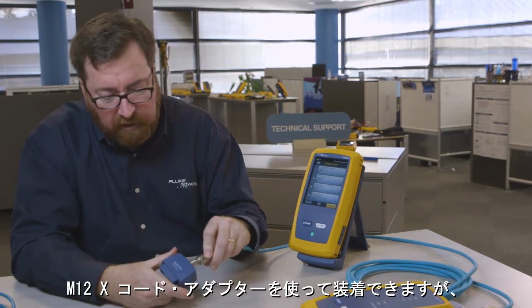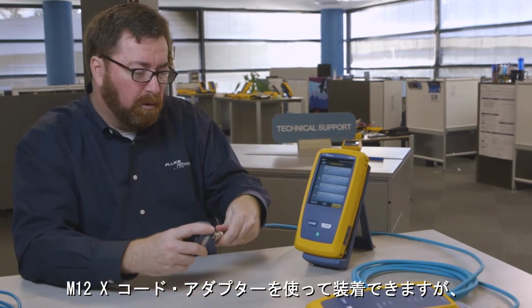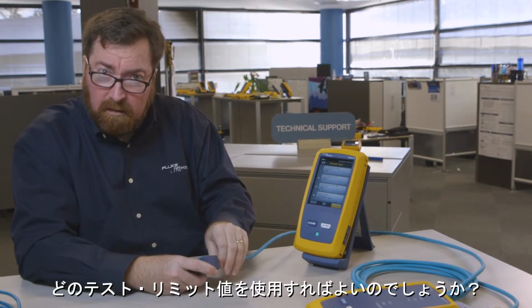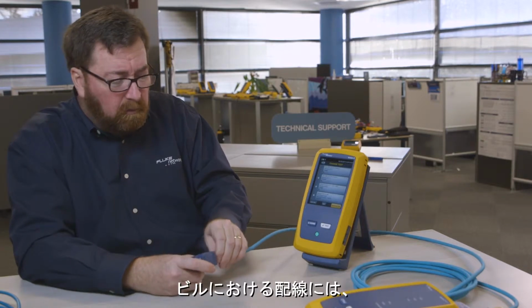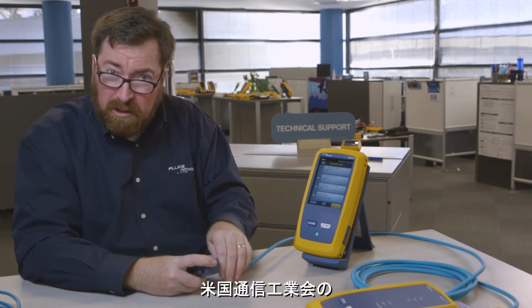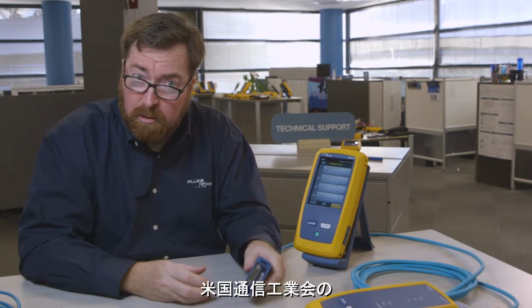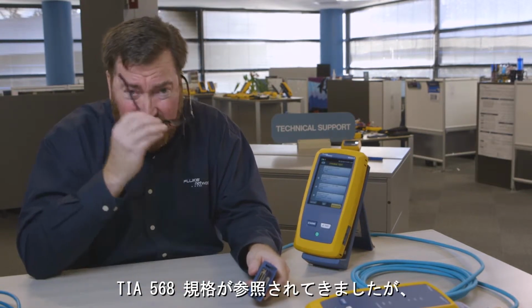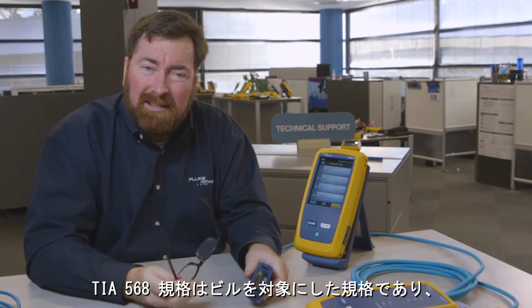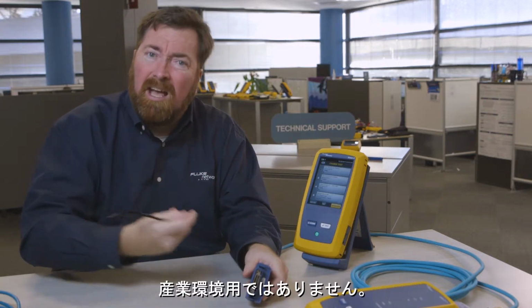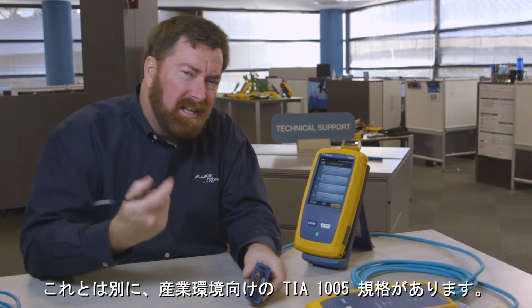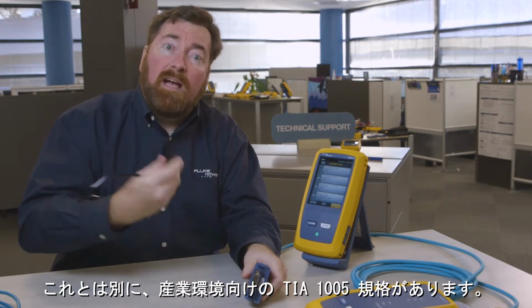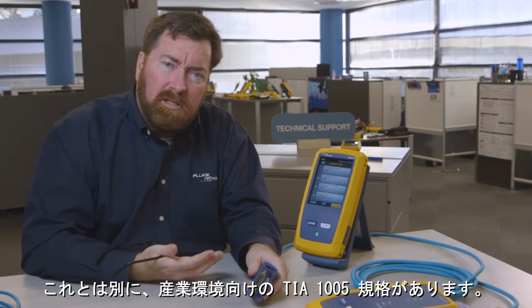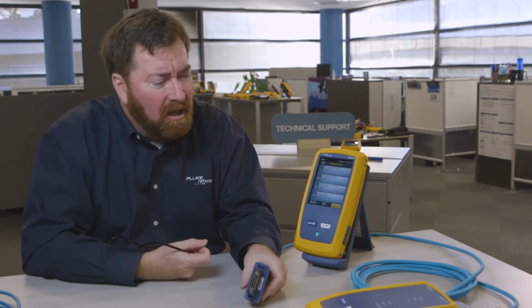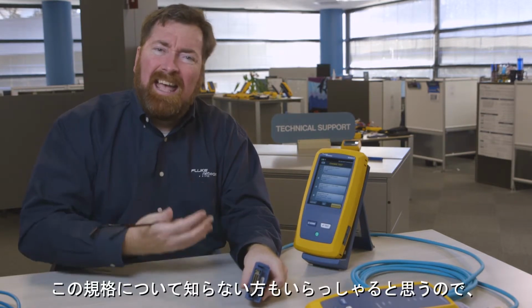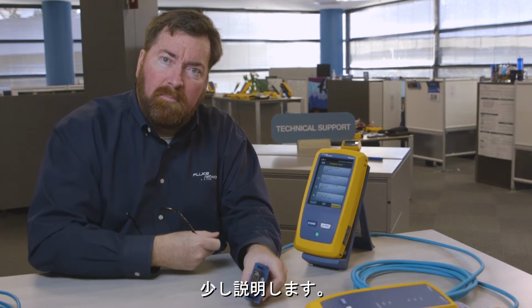It helps to have this M12 Xcoded adapter to put it on, but now what test limit am I going to use for this? Well, from the building world, we're used to talking about the Telecommunications Industry Association, the TIA 568 standard. But the TIA 568 standard is for buildings, not industrial environments. TIA does have a standard, the 1005 standard, designed to be used in industrial environments.